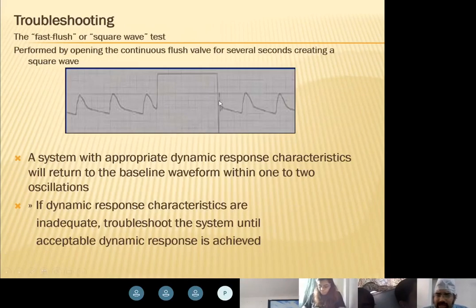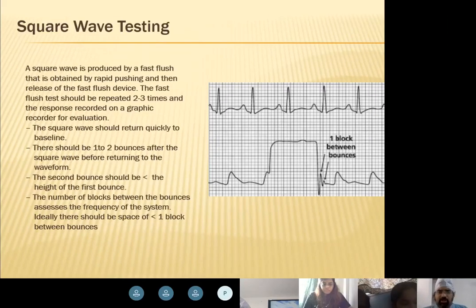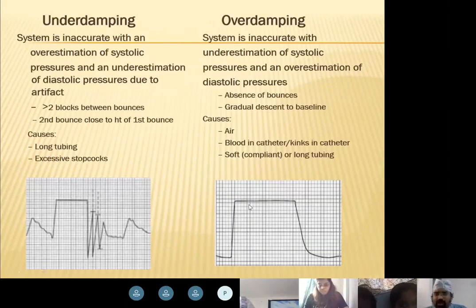If the fast flush test shows a square waveform with one big wave and one small wave, this indicates that the arterial waveform is okay. This is a problem of the patient. But if you have something very different, on the right side you have a square waveform, and do you see those two oscillations? No, you don't. When you don't see those two oscillations, that means the waveform is overdamped. Since they were not there, that is called an overdamped waveform.